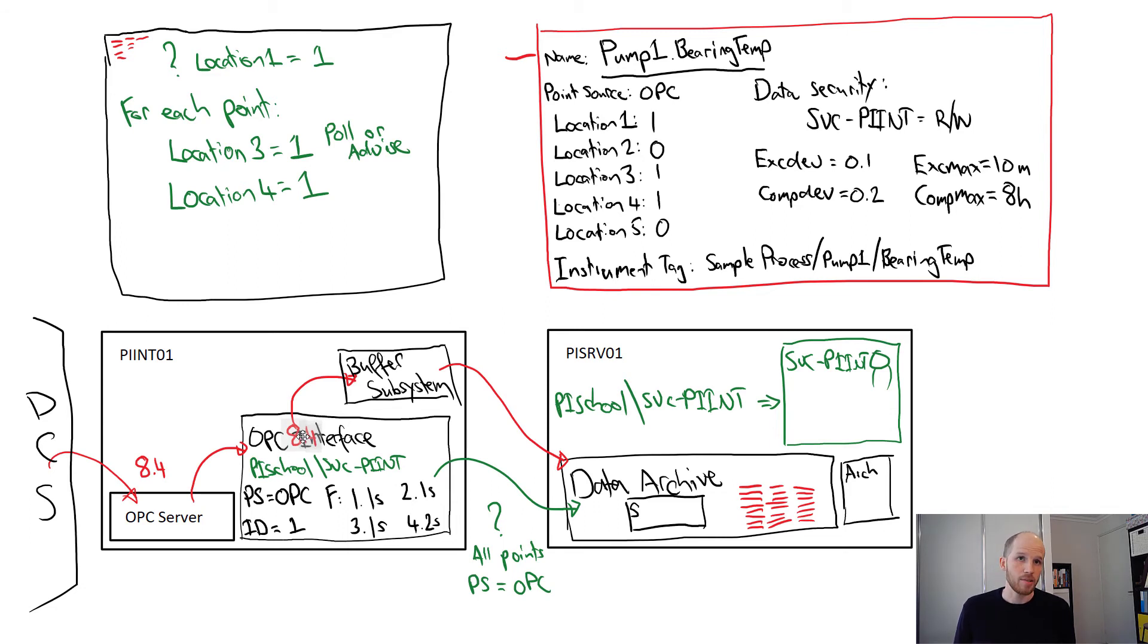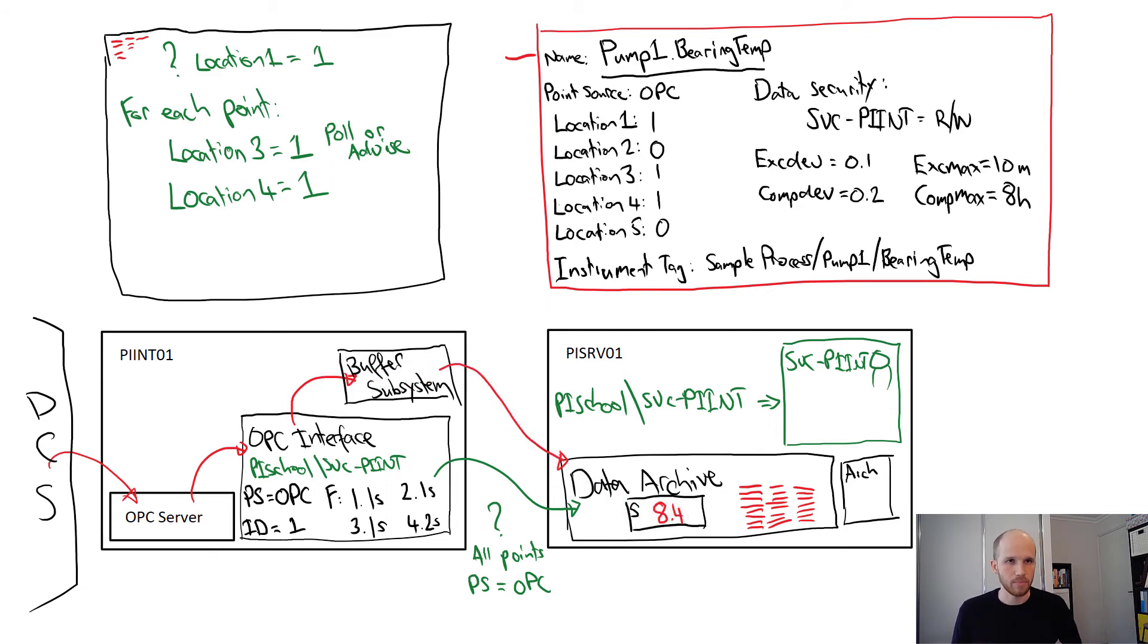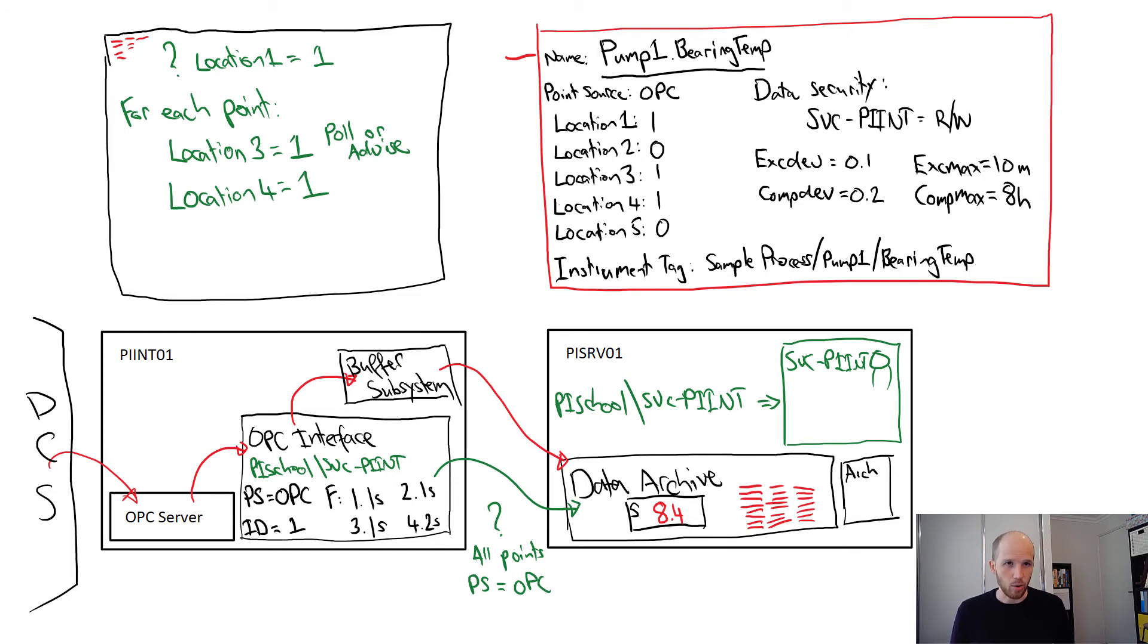The interface tests this value using a test called exception. If it passes, it sends the event through to the buffer, which in turn sends it through to the data archive. It gets stored to the snapshot, ready to be read by reports and dashboards, and it'll automatically be fed through to users that are looking at a real-time trend.